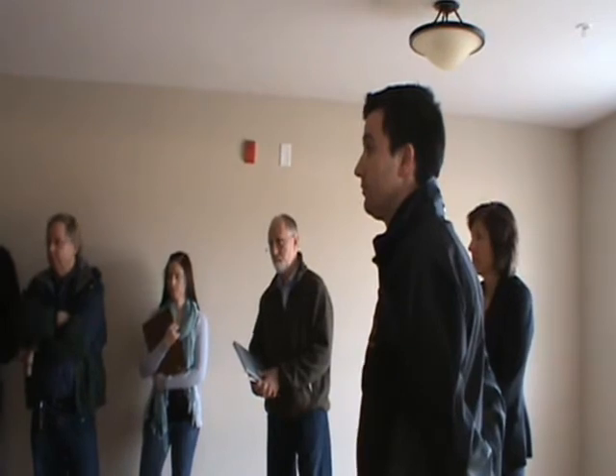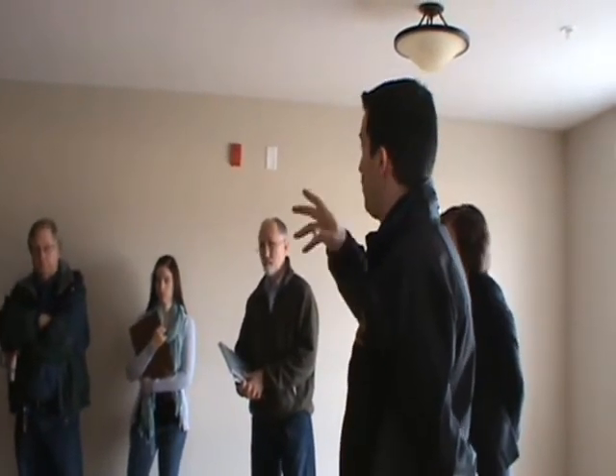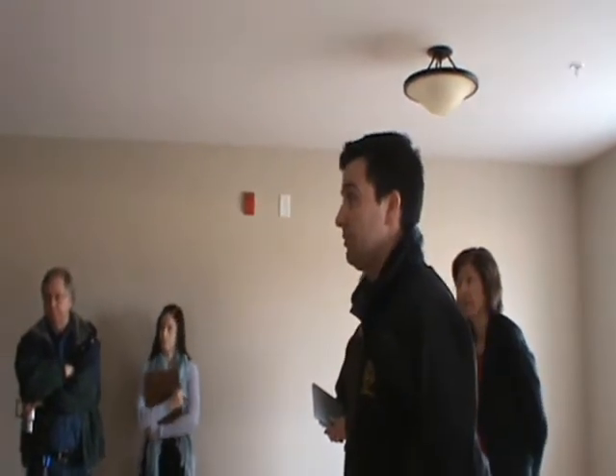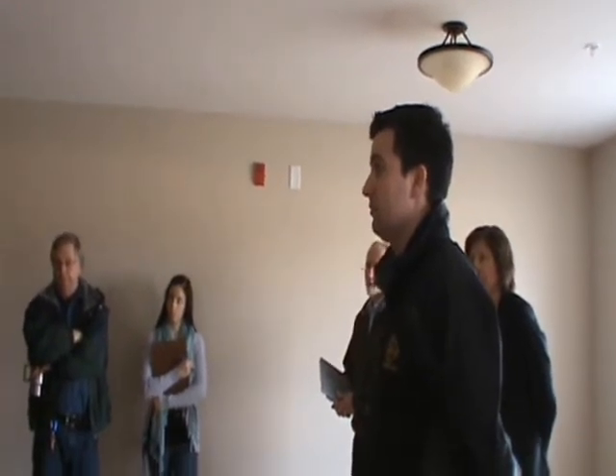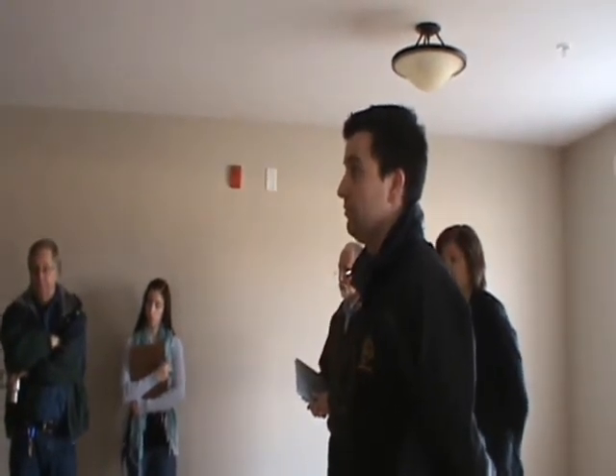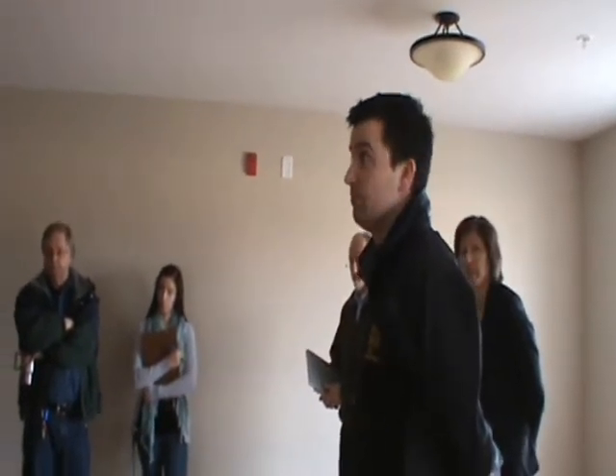And the other space up there is if somebody wanted to have a strobe installed for hearing impaired. The way that the strobe works is that spot for a strobe actually comes off the smoke detector. So upon request, there can be a strobe put in that's only tied to that smoke detector. So it won't strobe if the main building alarms go off. Exactly. It's just tied into the smoke detector. Is that normal? I guess it must be, if the engineer okayed it.